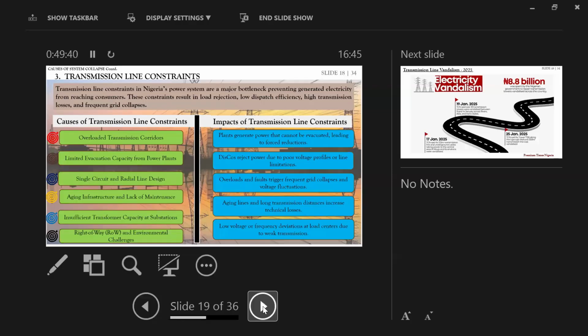One of the causes of transmission constraint is overloaded transmission corridors. An example is the Benin-Onitsha line. The 330 kV Benin-Onitsha line is one of the busiest in the national grid. Due to poor redundancy and high load transfer to the southeast, the line often operates near or above safe thermal limits, especially during peak demand, resulting in load shedding or curtailment of generation from nearby plants, e.g., Azura IPP, to prevent line trip.